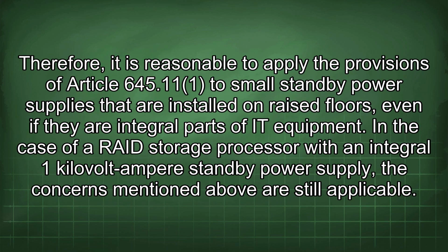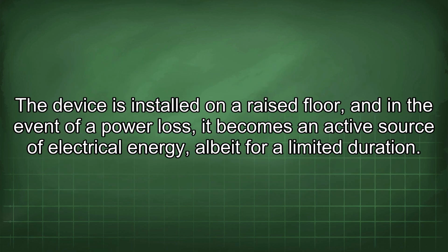Therefore, it is reasonable to apply the provisions of Article 645.11 onto small standby power supplies that are installed on raised floors, even if they are integral parts of IT equipment. In the case of a RAID storage processor with an integral 1 kilovolt-ampere standby power supply, the concerns mentioned above are still applicable. The device is installed on a raised floor, and in the event of a power loss, it becomes an active source of electrical energy, albeit for a limited duration.